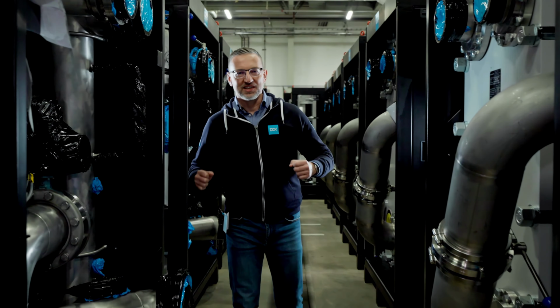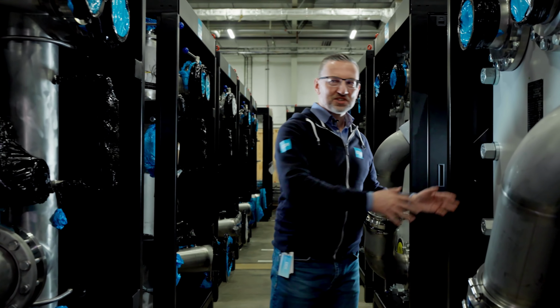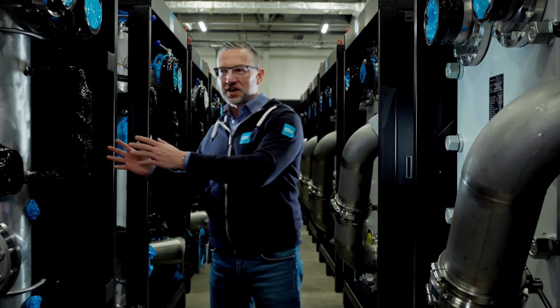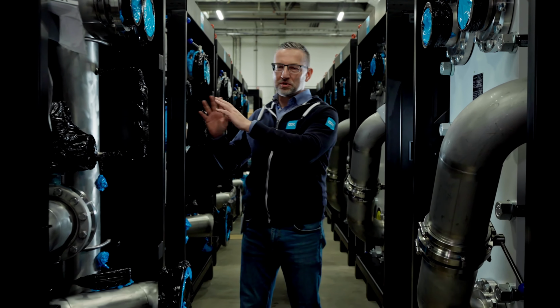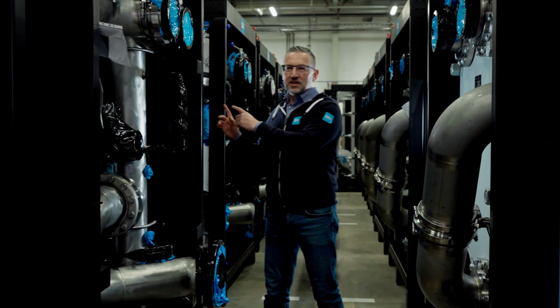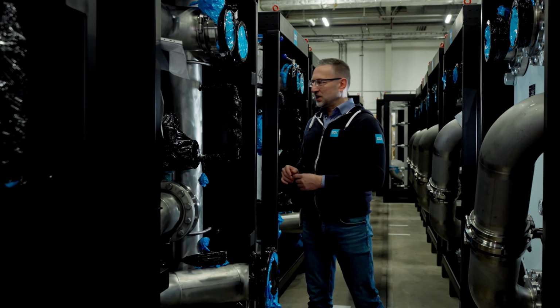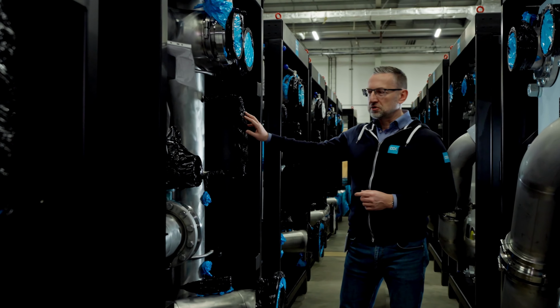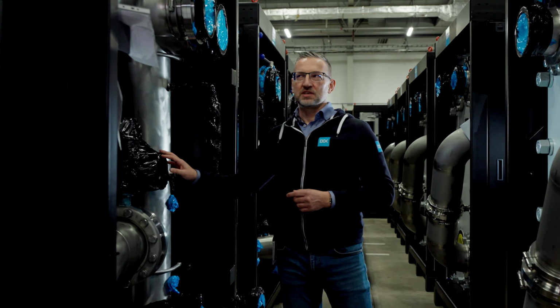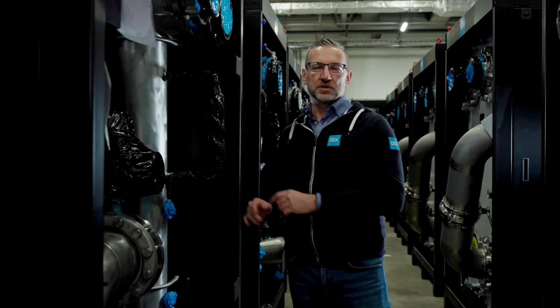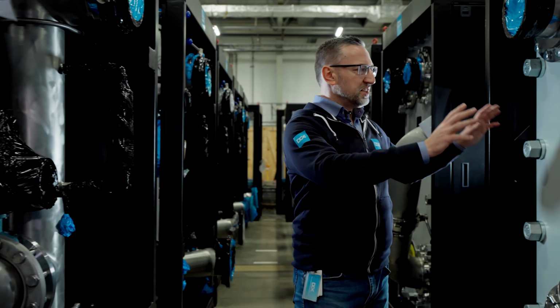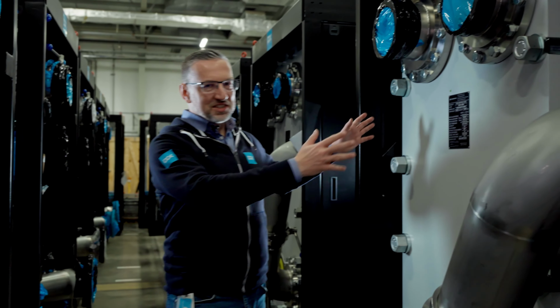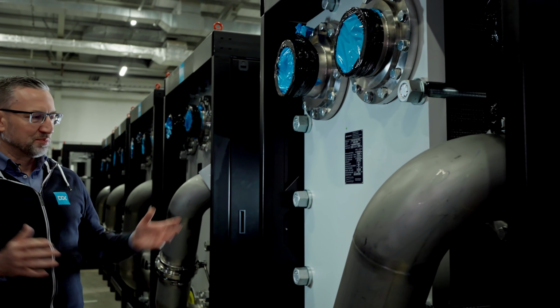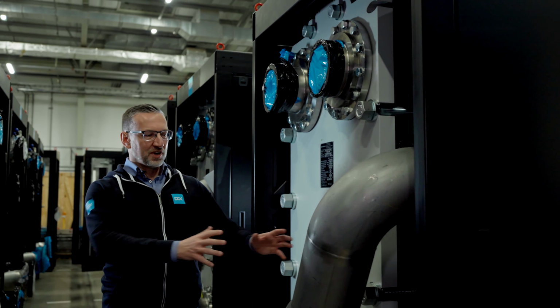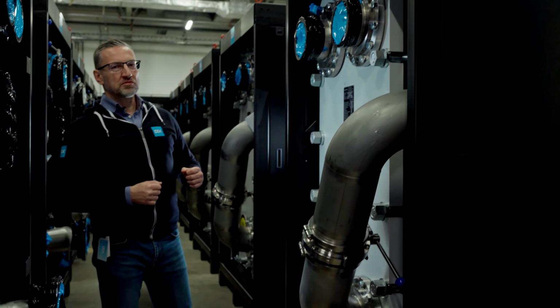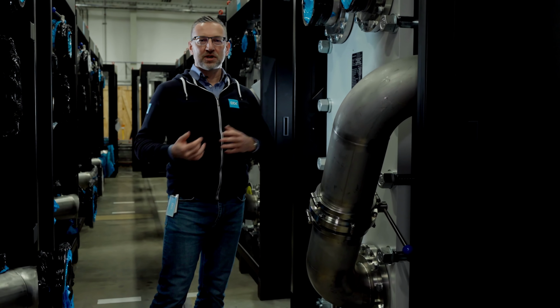So that's one side of the CDU, and that's the other side of the CDU. That's the C-frame, and that holds all the important pipe assemblies, control panel, pumps, inverters or VFD drives, sensors, and bypasses, valves, everything that's important for the CDU to operate. And that's the H-frame. As you can see, the biggest heat exchanger which anyone put inside a CDU system with large diameter pipes, and that covers the facility and primary loop side.